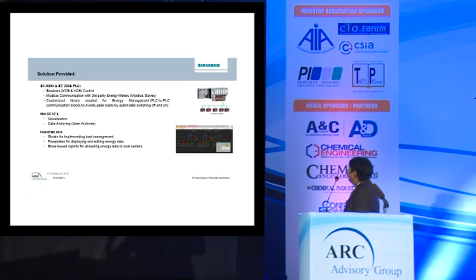Also, we have PLC to PLC communication, building to building. Two local PLCs communicate on the same network, and at the same time they report to the central processor. And SCADA for visualization is where you can monitor which breakers are switched on, what data the energy is consuming - just monitoring, data archiving, and controlling.